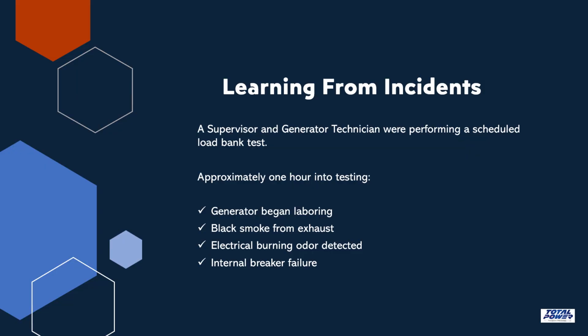A supervisor and generator technician were performing a scheduled 2-hour load bank test on a generator. Approximately 1 hour into the test, the crew noticed something unusual. The generator began laboring. Black smoke was observed coming from the exhaust. Almost immediately afterward, the crew detected the smell of burning electrical components. These abnormal operating conditions indicated something was seriously wrong.